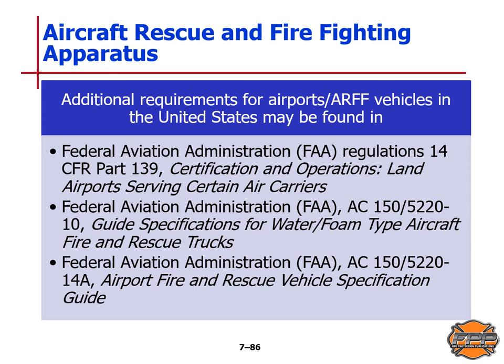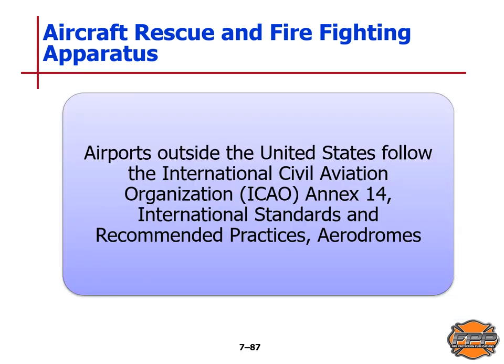Additional requirements for ARFF vehicles in the United States are found in FAA regulations 14 CFR Part 139 (Certification and Operations: Land Airports Serving Certain Air Carriers), FAA AC 150/5220-10 (guide for water-foam type aircraft rescue trucks), and FAA AC 150/5220-14A (airport fire and rescue vehicle specification guide). Airports outside the United States follow ICAO Annex 14 — the international standards and recommended practices for aerodromes.